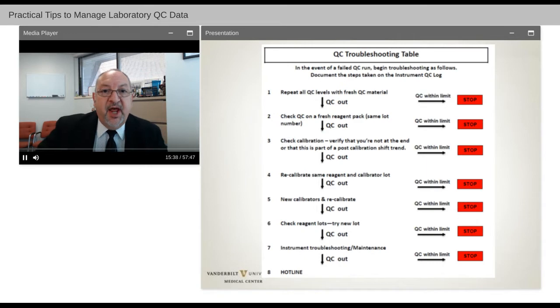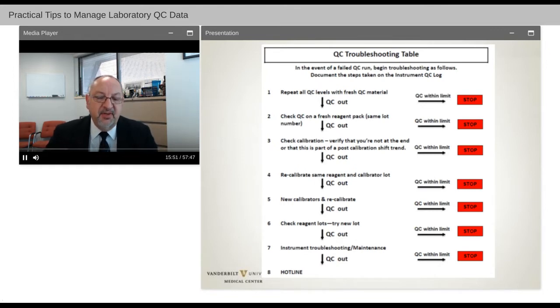We put out in our laboratory and post a troubleshooting table to assist our bench techs in how to troubleshoot out of range QC. First, we recommend going back and repeating the quality control. And this isn't just the level that failed. If we're running two or three levels of QC, we want the entire event to be repeated and make sure that all three of those levels, if we are running three level, multiple level QC, is within range. If it is, we can stop troubleshooting.